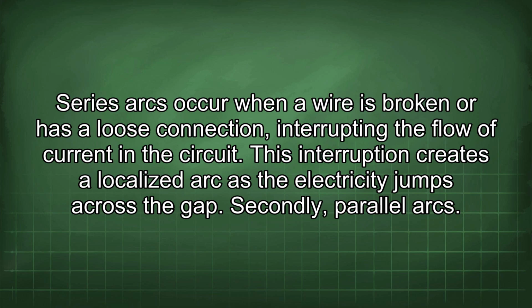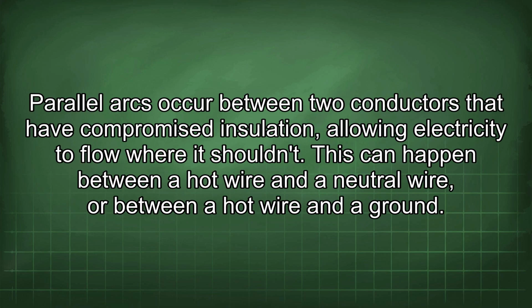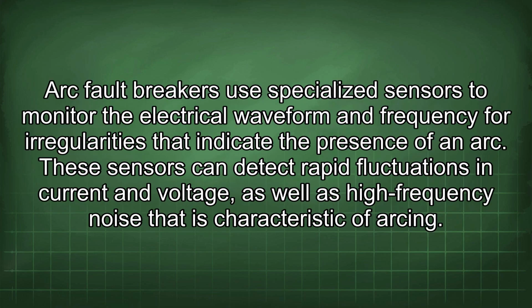This interruption creates a localized arc as the electricity jumps across the gap. Secondly, parallel arcs. Parallel arcs occur between two conductors that have compromised insulation, allowing electricity to flow where it shouldn't. This can happen between a hot wire and a neutral wire, or between a hot wire and the ground.